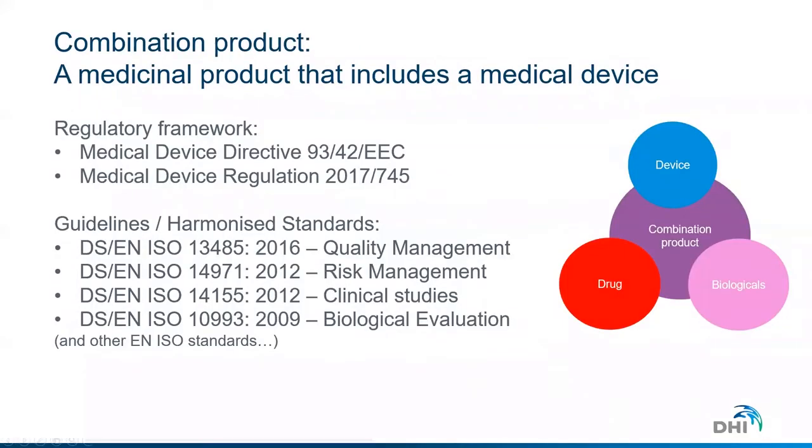And the regulatory framework for assessing and documenting the safety of a medical device is the medical device regulations. Currently, it's the Medical Device Directive in the EU that is the valid regulation. But from May 2020, the Medical Device Regulation will be enforced and be the regulation to consider when you have a medical device.